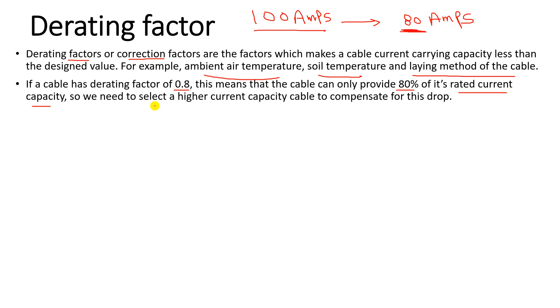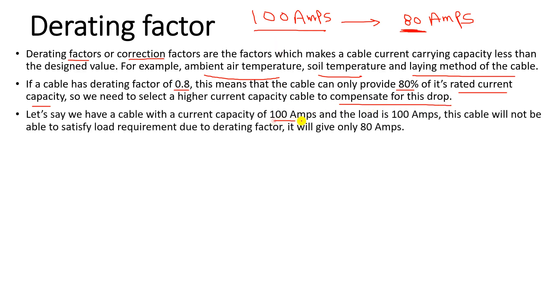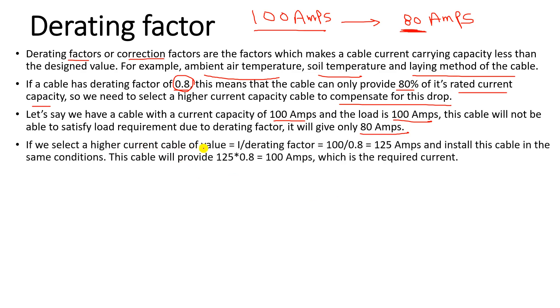To compensate for this drop, we need to select a cable with a higher current carrying capacity. For example, if our load is 100 amperes and the derating factor is 0.8, a 100-ampere rated cable will not satisfy the load — it will only deliver 80 amperes. We must select a cable with a higher rated current, calculated as: required current divided by the derating factor.